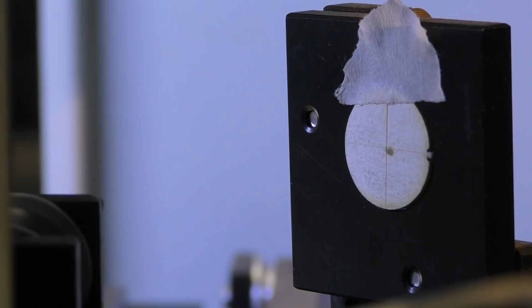So what we've got on mirror number 1 is we've got 3 adjusters. Now this mirror is arranged very nicely, so we can adjust X and Y independently. Now if you've got triangular as opposed to L-shaped adjusting screws, you're going to have a little bit more difficulty. This is very easy because we need to first of all adjust the spot very slightly upwards. So to get it to go up, we've got to twist the mirror backwards. If we leave these bottom 2 screws alone, we can just undo the top screw very, very slightly. Just make sure you undo all these adjusting screws, because we're not going to transport this halfway around the world, and these springs are going to lock it in place anyway.